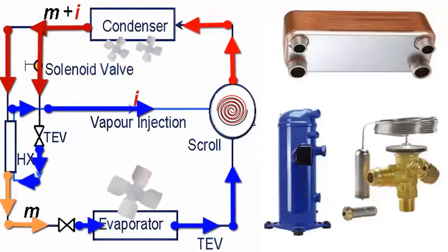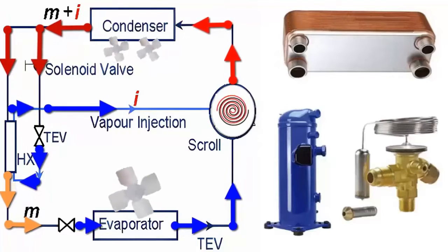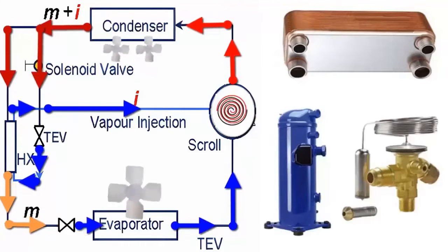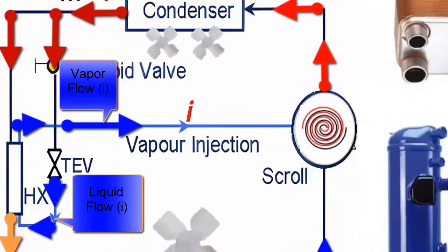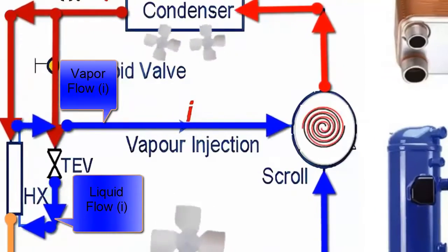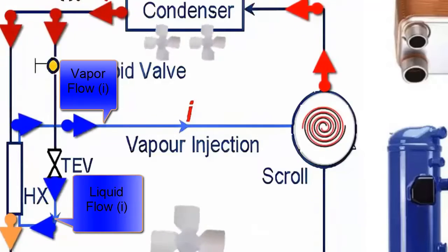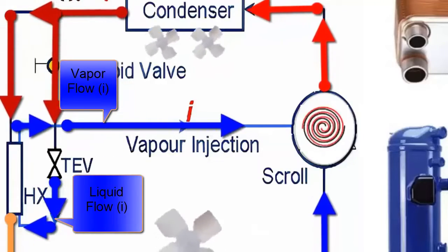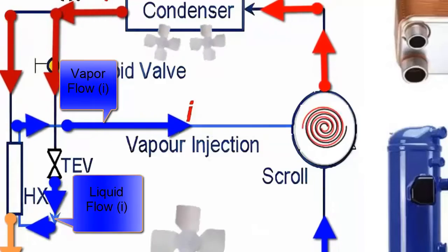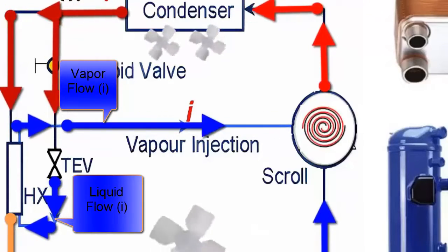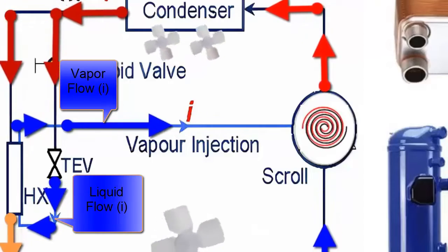The refrigerant flow, referred to as I, at the outlet of the expansion valve in the economizer system, changes from liquid to vapor in the HX exchanger. As it is still at a low temperature, it is injected back into the scroll compressor, providing additional cooling to the compression process, which is especially useful in high compression ratio applications such as freezing equipment.